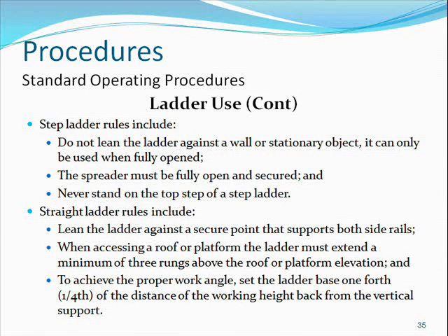Step ladder rules include: do not lean the ladder against a wall or stationary object. It can only be used when fully opened. The spreader must be fully open and secured, and never stand on the top step of a step ladder. Straight ladder rules include: lean the ladder against a secure point that supports both side rails.